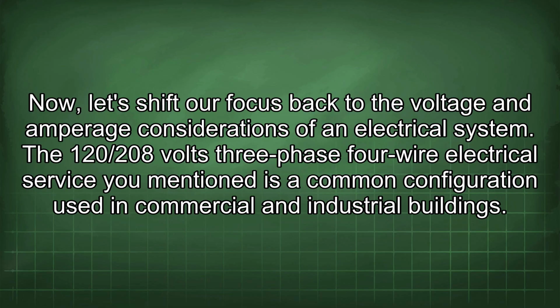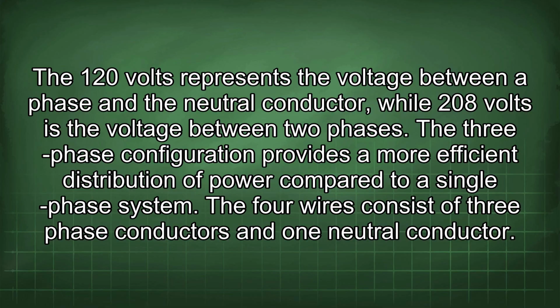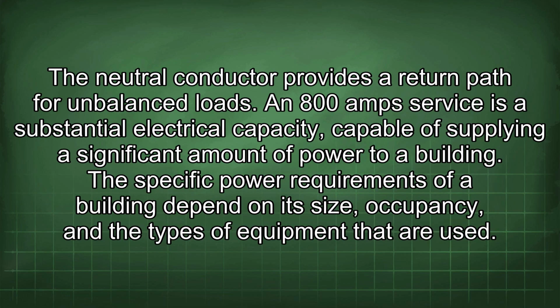Now let's shift our focus back to the voltage and amperage considerations of an electrical system. The 120/208 volts 3-phase 4-wire electrical service you mentioned is a common configuration used in commercial and industrial buildings. The 120 volts represents the voltage between a phase and a neutral conductor, while 208 volts is the voltage between two phases. The 3-phase configuration provides a more efficient distribution of power compared to a single-phase system. The 4 wires consist of 3-phase conductors and 1 neutral conductor. The neutral conductor provides a return path for unbalanced loads.